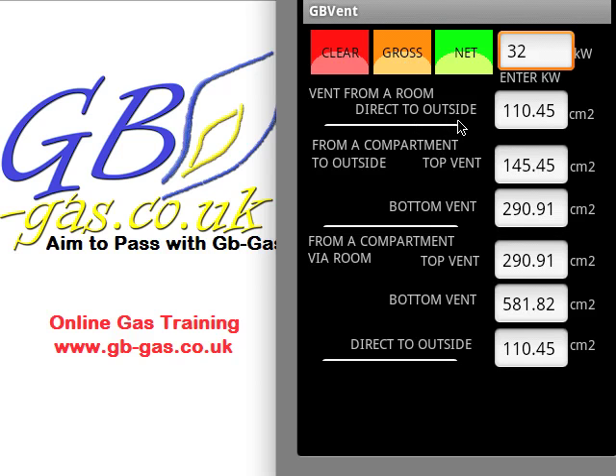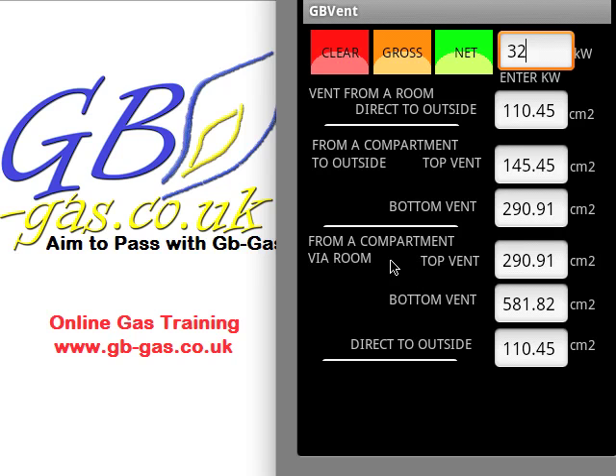This then gives the calculations. To vent an open flued appliance directly to outside, we would need one vent of 110.45 cm². If it's from a compartment vented direct to outside, we need a top vent of 145.45 cm² and a bottom vent of 290.91 cm². If we're venting via a room from the compartment, the compartment itself needs a top and bottom vent of those sizes, but we also need a vent direct to outside of 110.45 cm².